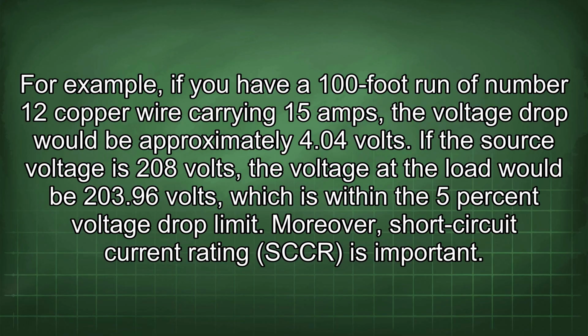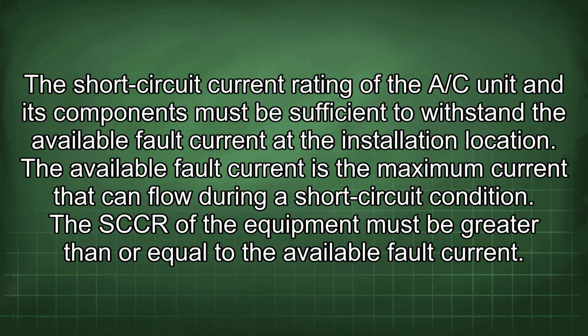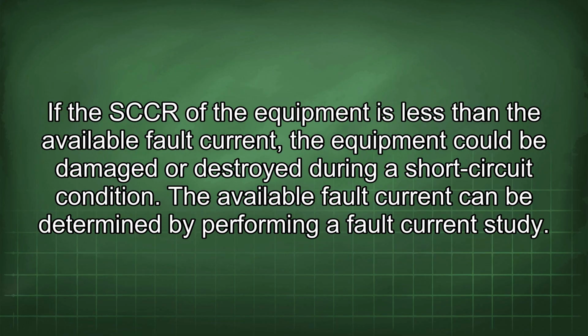5% voltage drop limit. Moreover, short circuit current rating, SCCR, is important. The short circuit current rating of the A/C unit and its components must be sufficient to withstand the available fault current at the installation location. The available fault current is the maximum current that can flow during a short circuit condition. The SCCR of the equipment must be greater than or equal to the available fault current. If the SCCR of the equipment is less than the available fault current, the equipment could be damaged or destroyed during a short circuit condition.